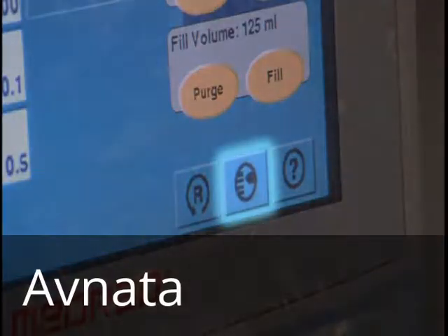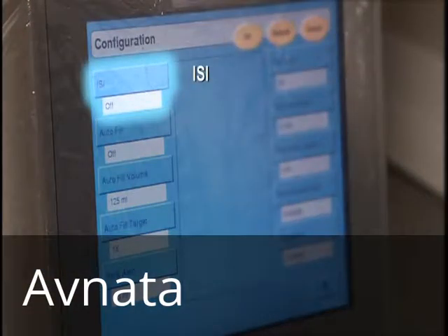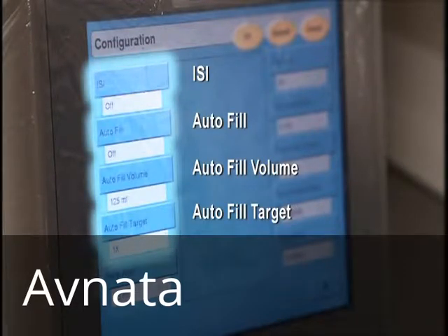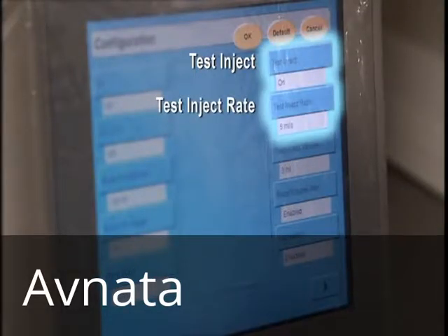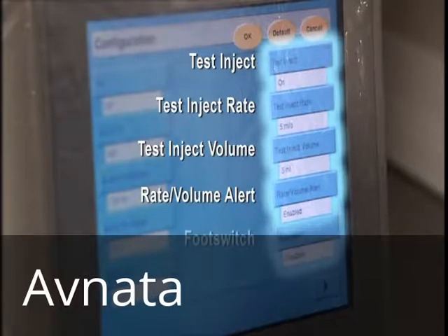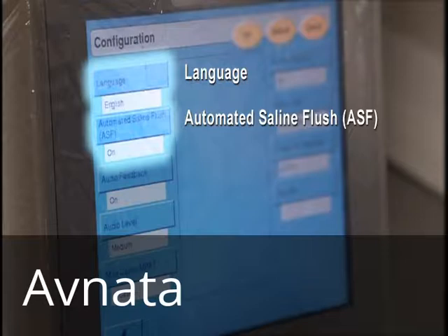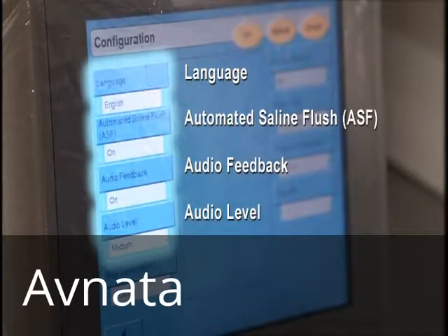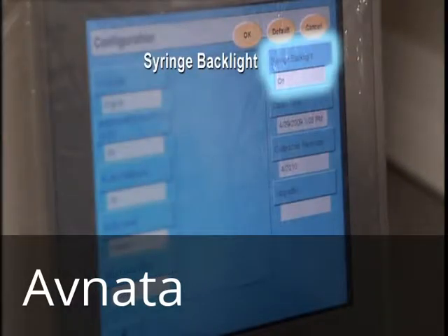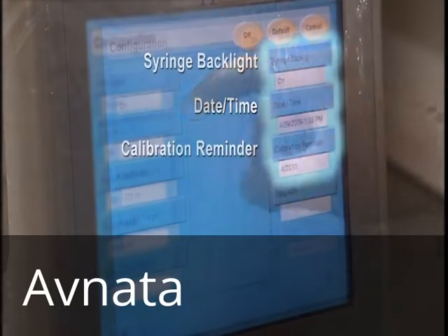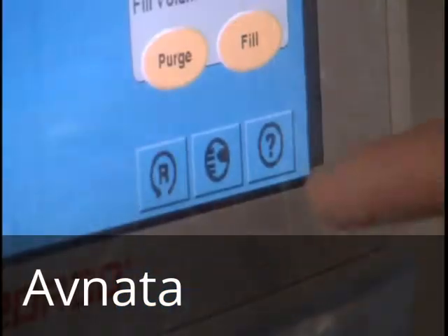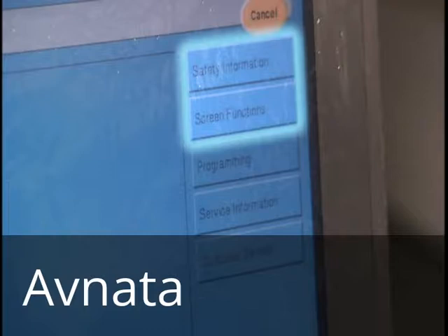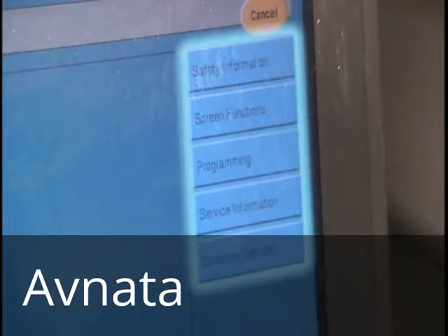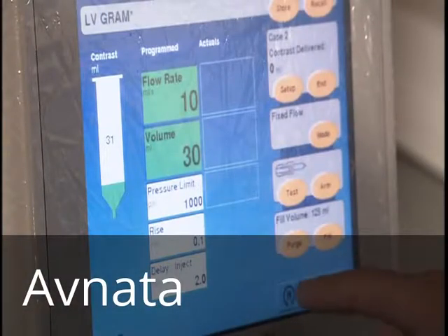Additional features of the DCU include Configuration, Help, and Reset. The configuration icon allows the selection of configurable options and preferences. These include ISI, Autofill, Autofill Volume, Autofill Target, Refill Alert, Test Inject Rate, Test Inject Volume, Rate Volume Alert, Foot Switch, Language, Automated Saline Flush, or ASF, Audio Feedback, Audio Level, Max Cases per MPAT, Syringe Backlight, Date, Time, and Calibration Reminder. Touch the appropriate button for more information. Help includes the safety information, screen functions, programming, service information, and customer service. Reset is used to return programmed parameters to factory default settings.